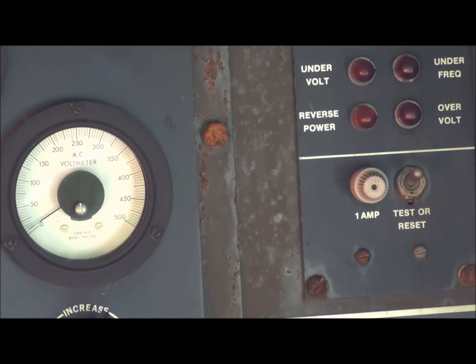This actually is pretty normal behavior, to see the voltage spike like that on the startup. The field flash generates that high voltage spike. So I believe it's just a set point issue. We'll go ahead and demonstrate what's going on here, and then I'll open up the tech manual and we'll figure out how to get it adjusted.